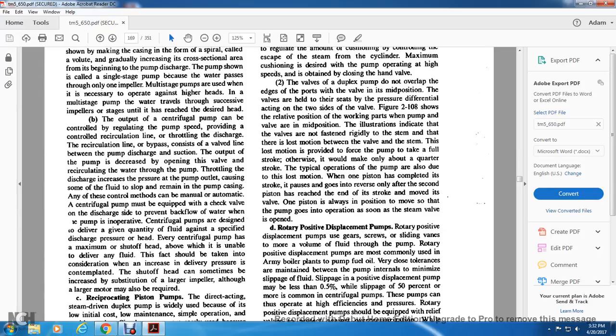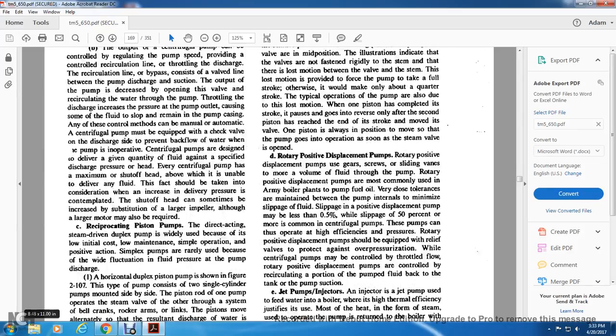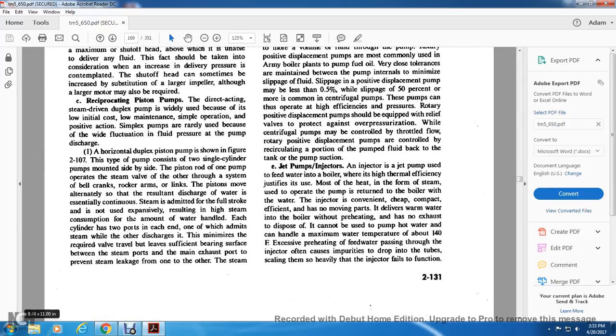Centrifugal pumps are designed to deliver a given quantity of fluid against a specified discharge pressure head. Every centrifugal pump has a maximum shutoff head above which it is unable to deliver any fluid. This fact should be taken into consideration when increasing delivery pressure. The shutoff head can sometimes be increased by substituting a larger impeller, although larger motors are also required.